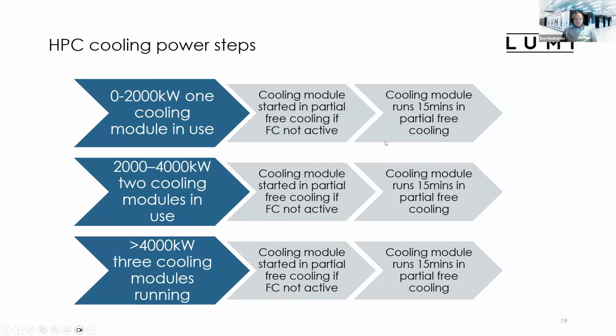So about this HPC cooling power steps, we had those 3 cooling modules. So from 0 to 2 megawatts, we have 1 cooling module in use. And every 2 megawatt steps, we are starting another one. And over 4 megawatt, we are running all 3 cooling modules. And always when we start a cooling module, it starts on the partial free cooling, which I will explain soon, if the free cooling is not active. So we are running these cooling modules in the partial free cooling 15 minutes on the cooling module start to make sure that heat pumps get stabilized and cooling is working as designed for the Lumi.